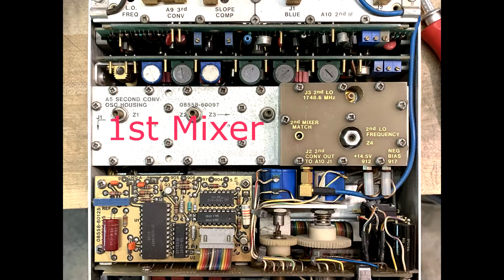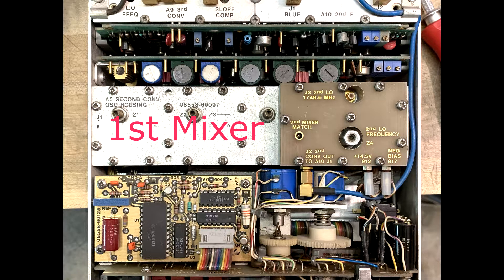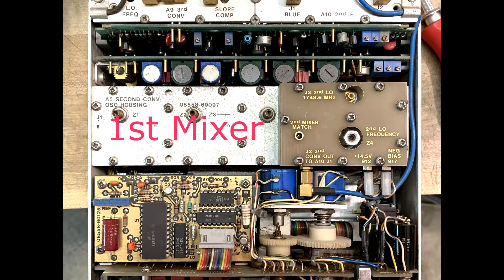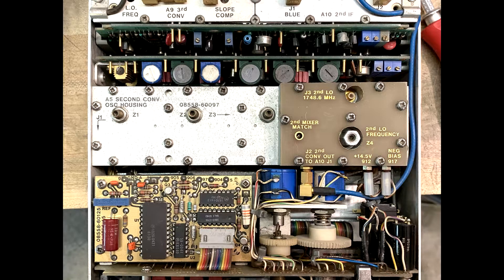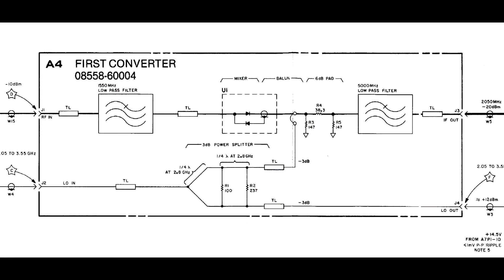The first mixer has a local oscillator that is a Yig oscillator. In the first mixer, we have also a low-pass filter and a power splitter. And the power splitter runs out to a BNC on the front panel, so you have access to the LO on the front panel if you want to add external test things that require you to have the local oscillator.